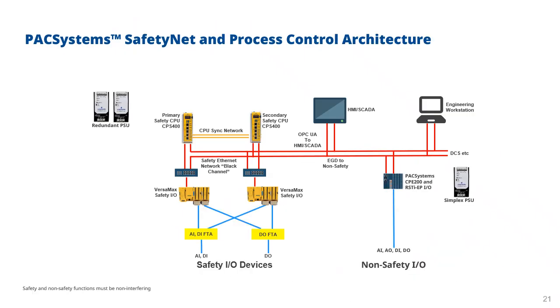So here's how we combine SafetyNet with process control. We do have that EGD communications, so using that simplex or dual network, we can link to a standard CPU. I'm not showing the full network architecture here. There might be additional switches required, but using a standard CPU such as a PACSystems CPE200 with Ethernet global data, then we can have the safety in the safety system inside PACSystems SafetyNet, and we can have the non-safety controls inside a standard PACSystems CPU.